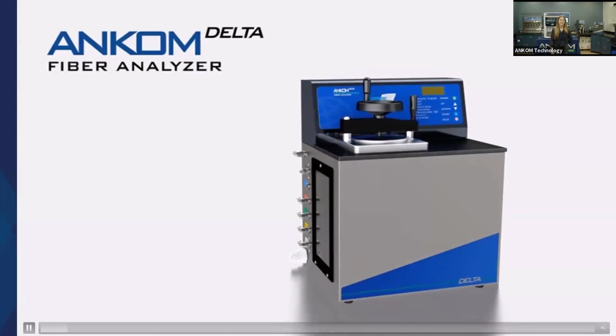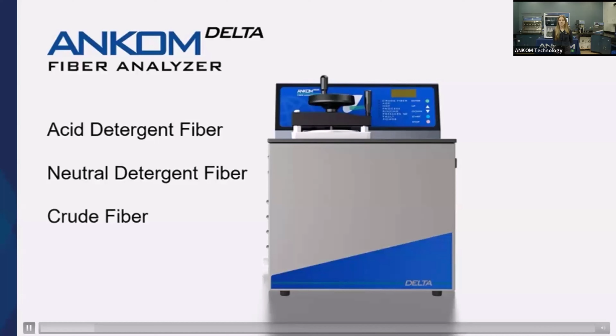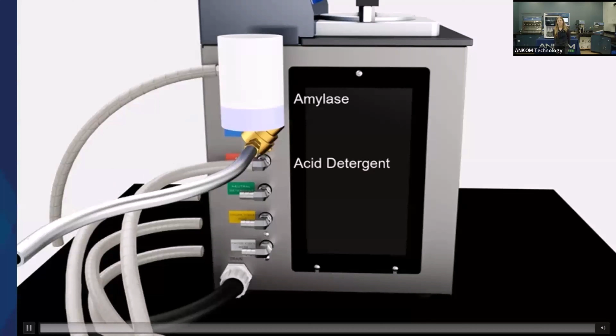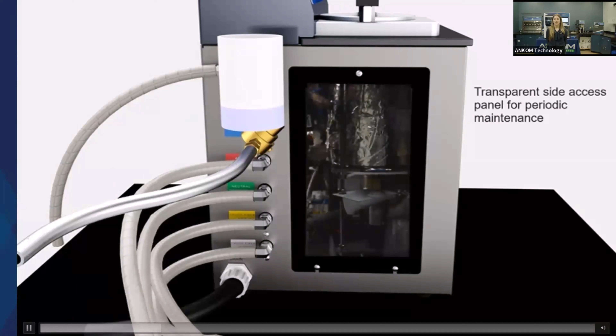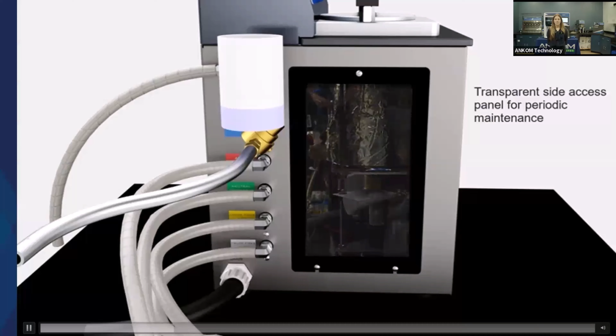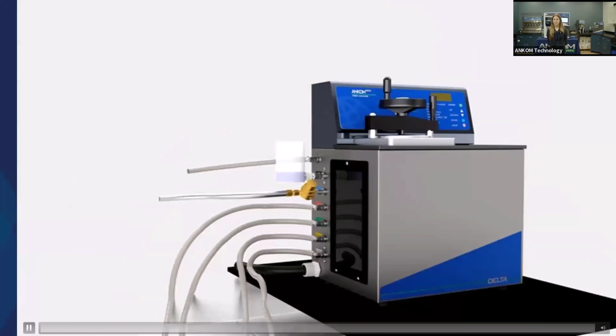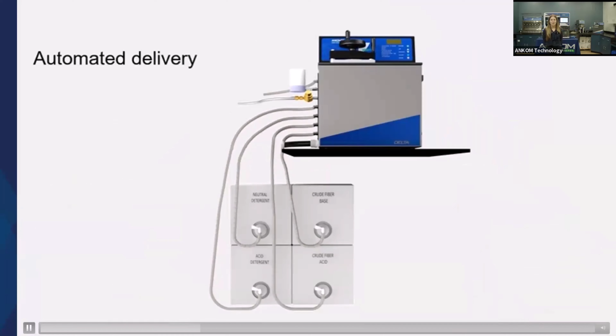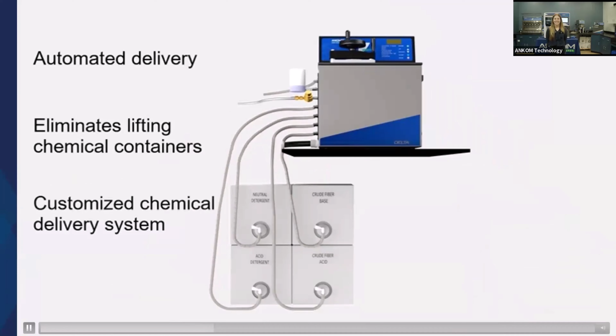The ANKOM Delta Fiber Analyzer provides an automated, easy-to-use method for determining acid detergent fiber, neutral detergent fiber, and crude fiber values in feeds and forages. The Delta achieves automation at the highest level with an internal pump system and 5 Easy Connect solution ports. Amylase, acid detergent, neutral detergent, crude fiber acid, crude fiber base. The addition of a transparent side access panel simplifies periodic maintenance and allows the user easy visual access. The internal pumping system allows the user to place any chemical container within range of the instrument for automated delivery. No gravity feed is necessary, therefore eliminating the need to lift heavy chemical containers, and enables the ability to connect the Delta to a larger chemical delivery system.